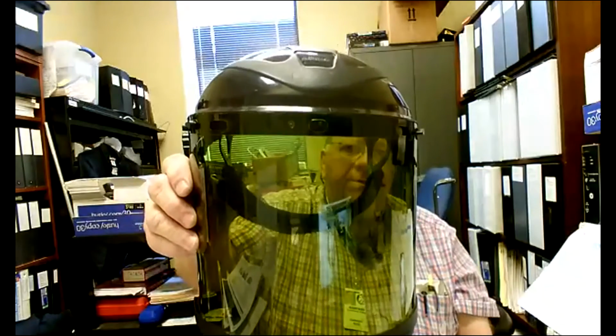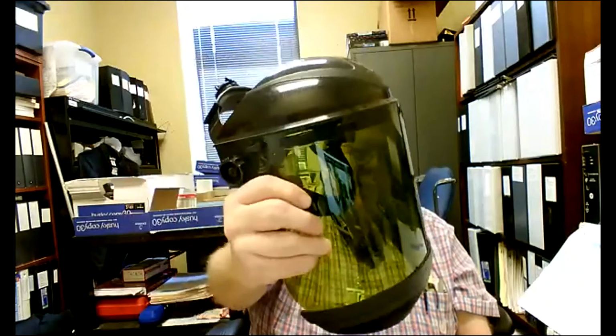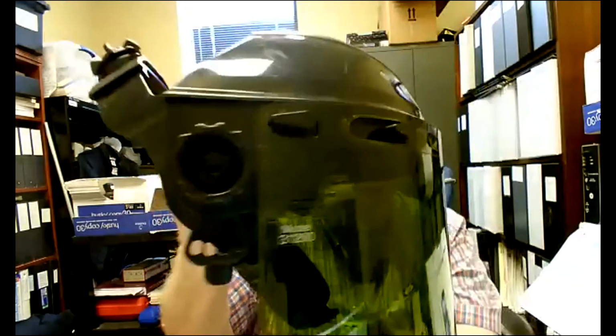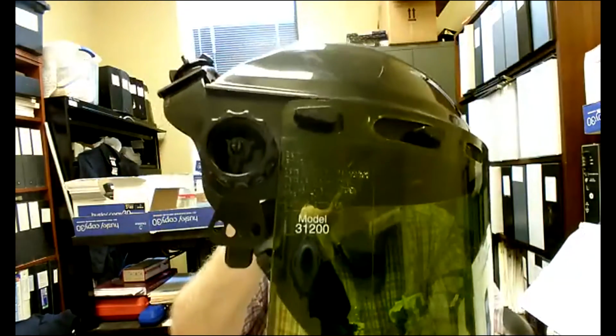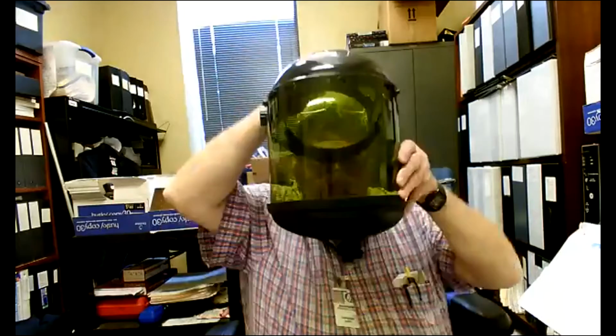And as far as that lab coat there, it'll protect you all up in here down to below your knee, for those of you that of course don't have the flame retardant clothing. And for your face protection, we've got a tinted, ARC rated face shield. The green color is a filter that filters out the super bright light that can happen when you have an ARC flash. There are ratings on these, as you can see on the side, that it's a listed type ARC flash shield. We've got one down there with an actual hard hat built onto it, but it's pretty bulky. But if you work in certain plants, then you have to have the hard hat version.